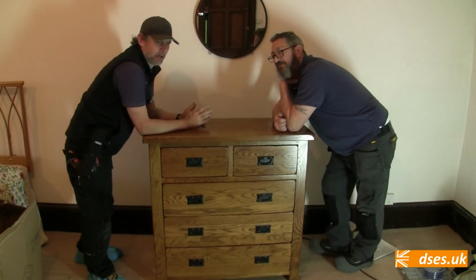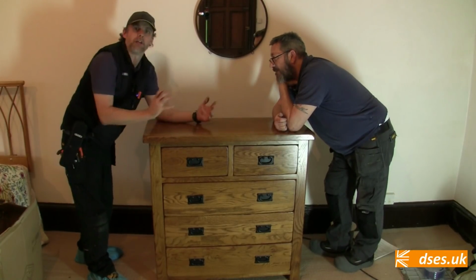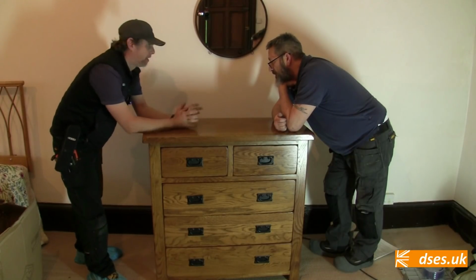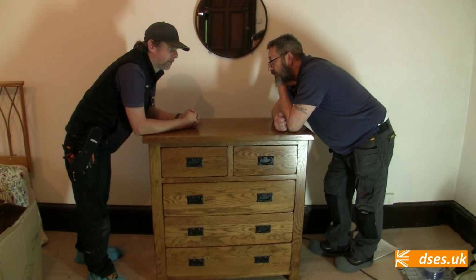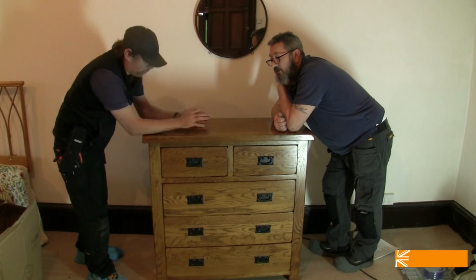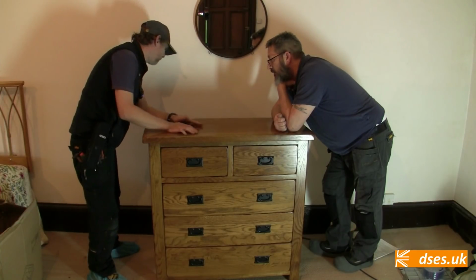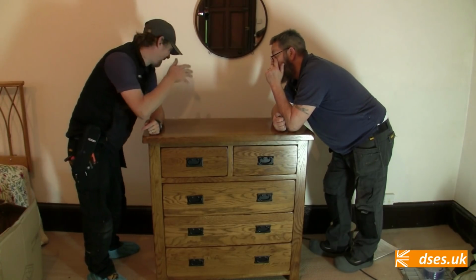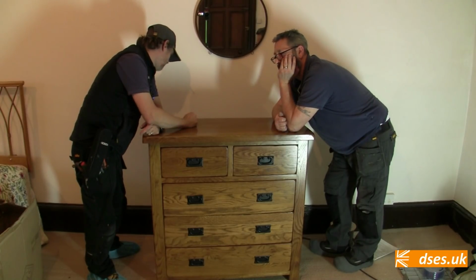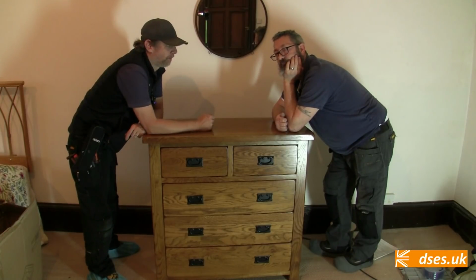We don't normally, well, you're going to make a determination on the EICR as to what furniture you're going to shift, because obviously you have to get to some electrical accessories. Some you can't get to because it's behind fitted furniture, like in a kitchen, for example. In a bedroom like this, we're not going to damage the floor by moving this out. It's a bit heavy. We could lighten the load by taking the drawers out, but we're just going to try and tip it forward, get rid of some of the spaghetti behind here and get to the socket outlet.